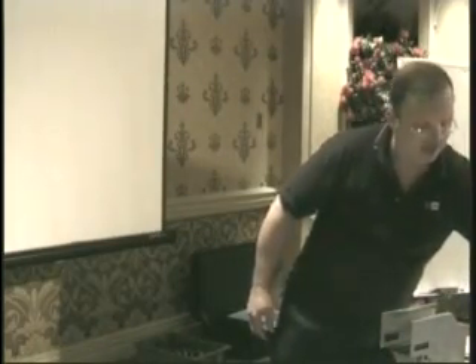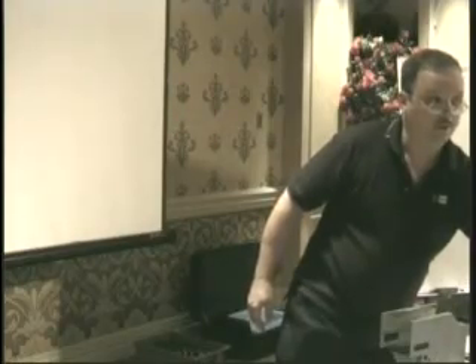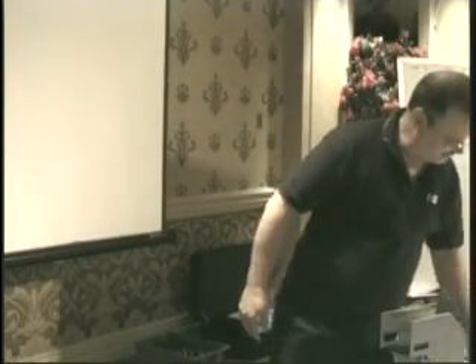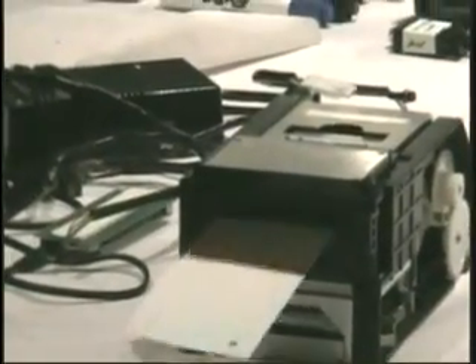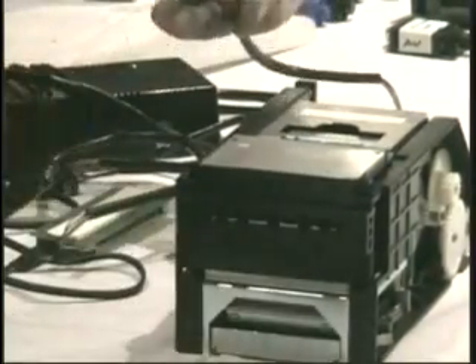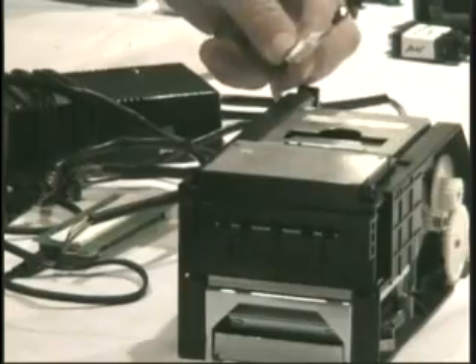If you've got it in the game and you're calibrating it, watch your bezel lights. Your bezel lights are hooked to the same circuit that this is. When it completes calibration, you're going to get a rapid set of pulses. Real fast flash. That's just letting you know that it's completed calibration. It's written it to the E-square. It's okay to go ahead and reset the dip switches back to their original position.